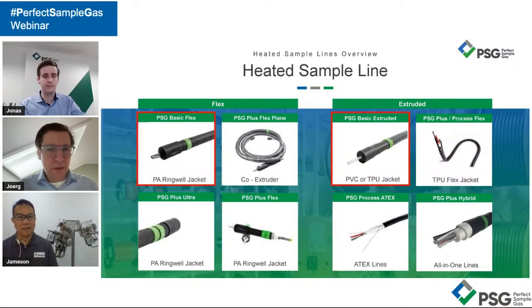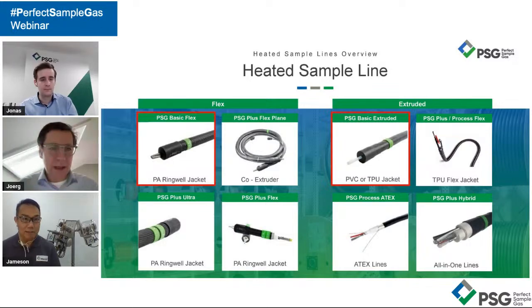In Asia, for CEMS applications, as far as my territory is concerned, I always wanted them to choose the flex line, whereas the extruded line has a slightly different definition. We use it on process lines, like gas chromatographs or mass spectrometers, to hold the sample at positive pressure and a certain temperature, whereas the flex line is different.